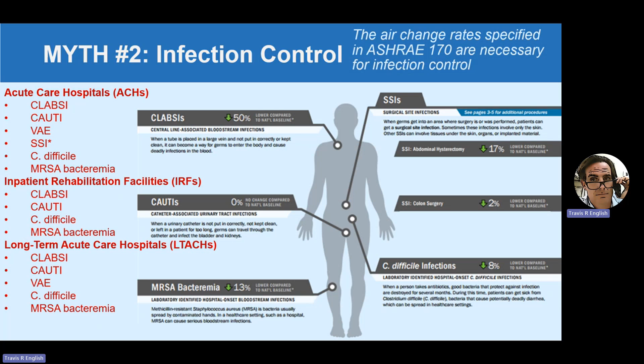There's not a body of evidence that points with a preponderance of evidence that ventilation at 20 air changes per hour is relevant in surgical site infection rates, right? And of course, more importantly, most of the healthcare ventilation requirements, 99% of them, are not in operating rooms. They're in all the other rooms. So in order for this myth to be true, ventilation would need to clearly influence infection rates in general areas, patient rooms, exam rooms, treatment rooms, etc. But it doesn't. Most of those HAIs are from direct contact, and they're totally unrelated to air quality.